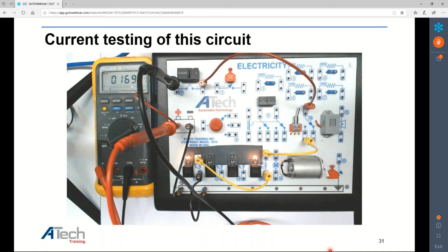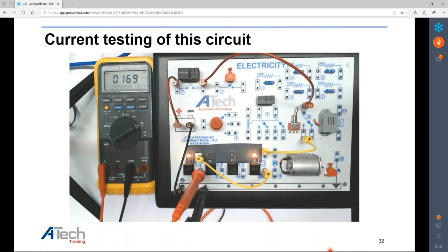I'm doing work. If I go to my next slide, I'm at the ground, on the ground side of that sensor's circuit to ground, measuring the amperage. I jumpered in series at the output of the circuit at the bulb and to ground, and got 169 milliamps. So no matter where I check the circuit, the amperage would be the same. But what changes? Voltage always changes, amperage stays the same. That's something to keep in mind when testing.